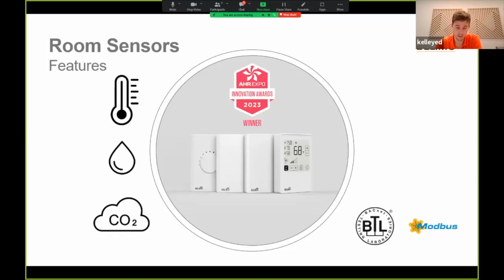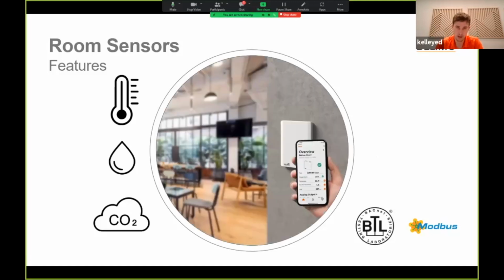Then we have active room sensors. They measure temperature, relative humidity, dew point, and CO2 concentration. They have analog outputs, so 0 to 5, 0 to 10, or 2 to 10 volts, or communication, so BACnet MSTP, Modbus RTU, or Belimo's proprietary MP bus. The cool thing about these room sensors is that all active room sensors are configurable through your phone by NFC.